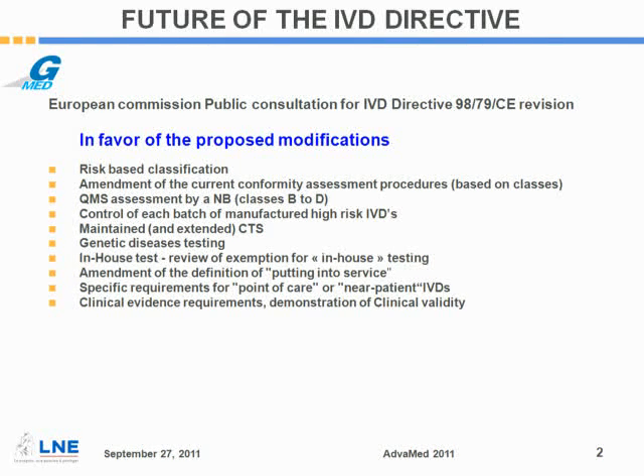That means for Class A IVD medical devices, the manufacturer will keep his technical documentation on site, but he also has to prepare a quality management system. But Class A should not be followed by a notified body. The others which will be followed by a notified body will be Class B, C, and D. What we can see in terms of trends is that for Class B and C, it will be mainly a review of the technical documentation on the manufacturer's side, which is what is done currently in comparison to the Medical Device Directive. And for Class D, it will be a review of the technical documentation on the notified body's side. So that's why I call it the QMS assessment by the notified body.